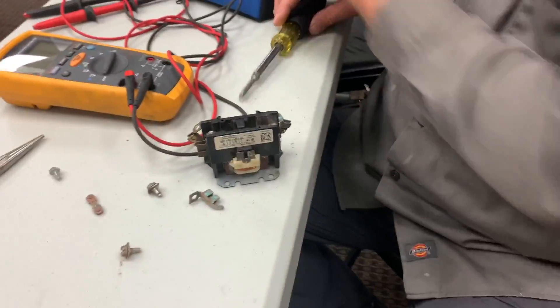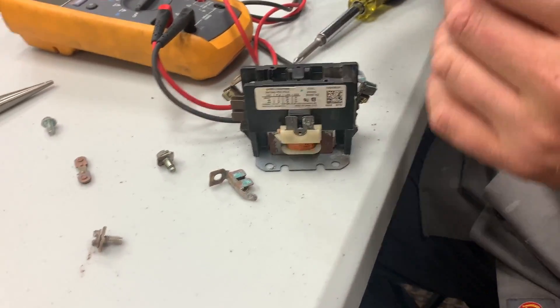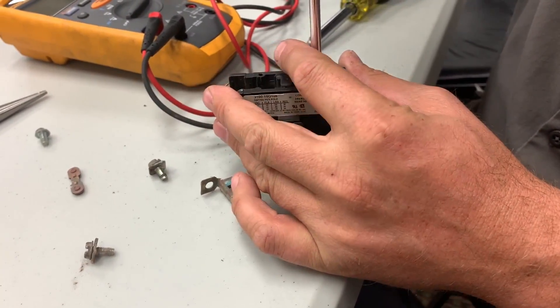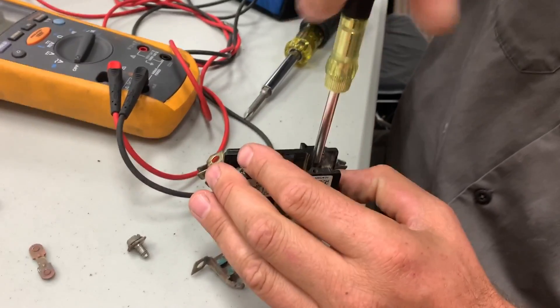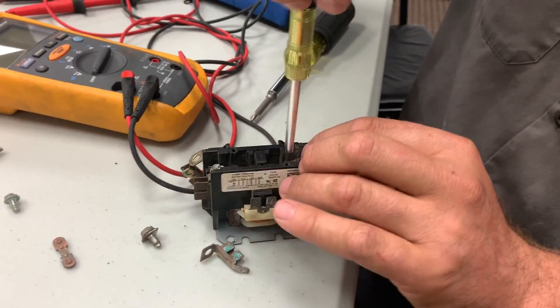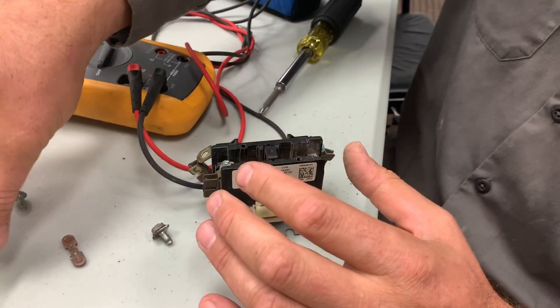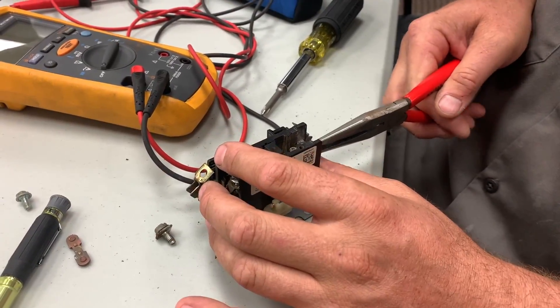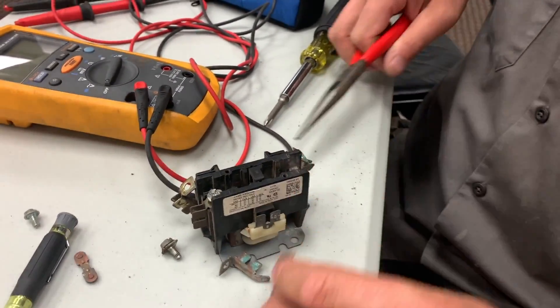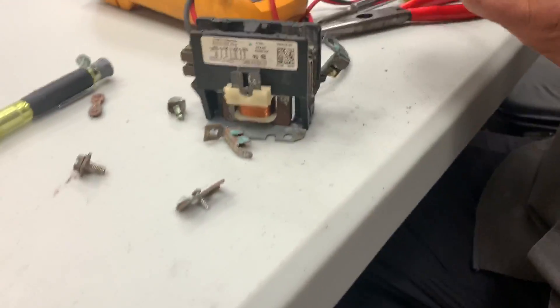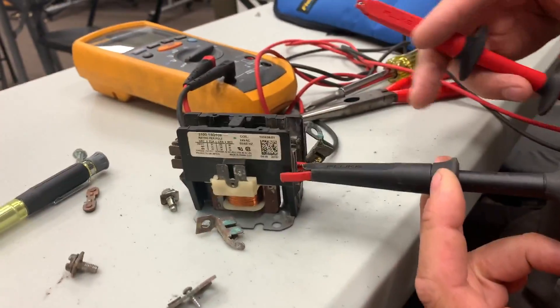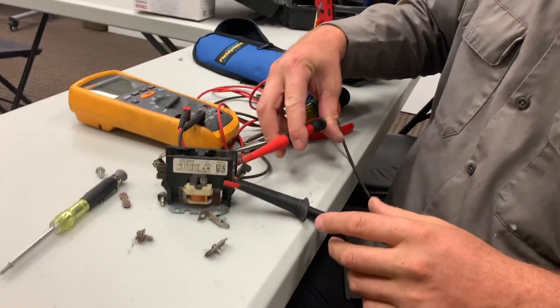This is a residential unit, just 240 volts. I think there may be a combo problem because one of the techs observed that the compressor wasn't starting at one point. Maybe the compressor drawing consistent high start amps could have resulted in more contact loss. As the thing is making and breaking, you have those big arcs. Some of that can be metallic material too, I would imagine. We got everything removed.